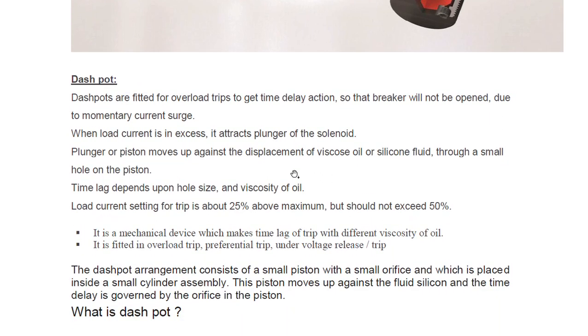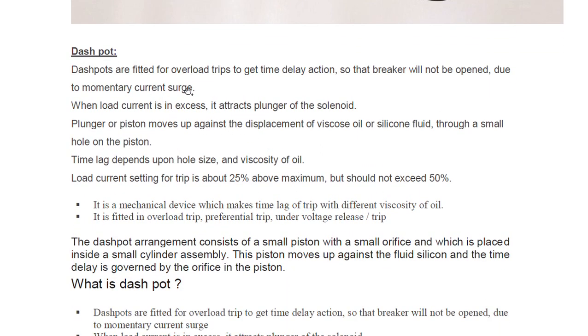Dashpots are fitted for overload trips to get time delay action due to momentary current surges. There is a momentary current surge, so the dashpot introduces a delay so that the breaker should not be opened. If there is a sudden surge in current, the breaker will suddenly open, causing a blackout and all machinery will shut down.